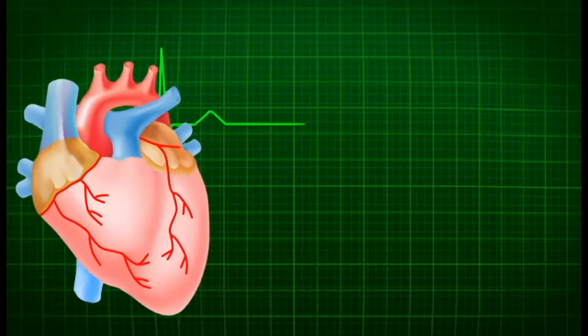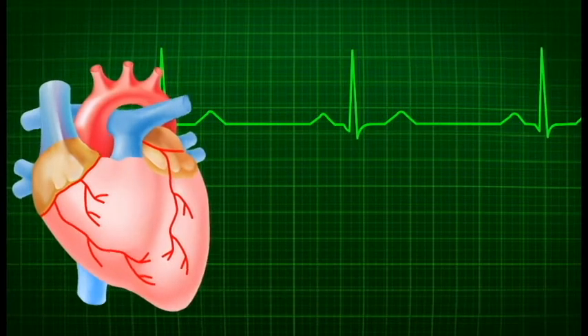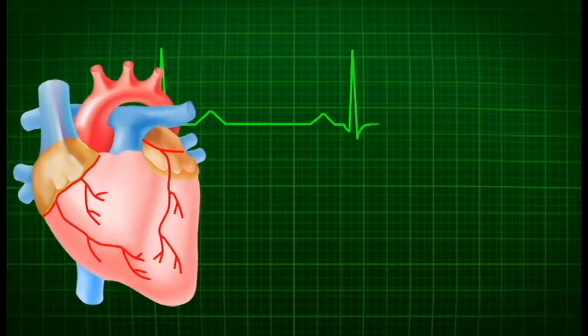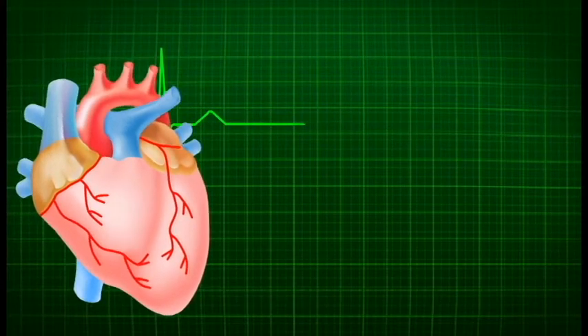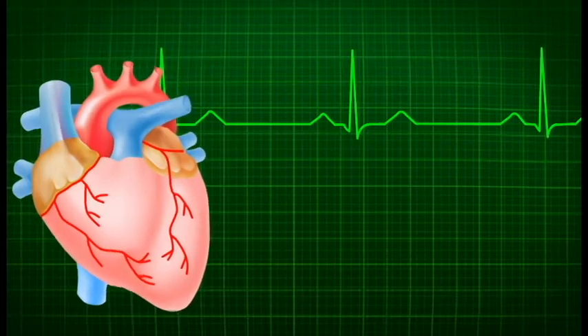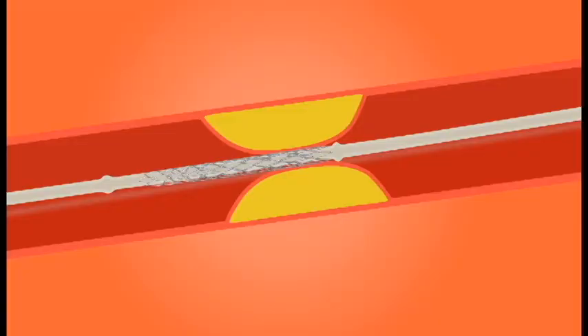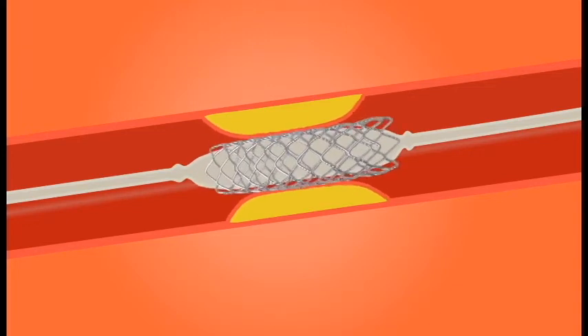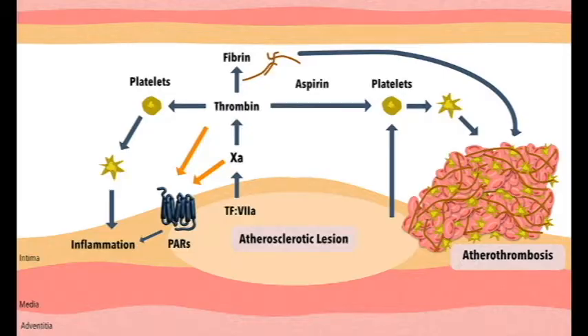As with most medical procedures, there are risks involved with the usage of bioresorbable stents. The first issue is that the recoil rate of the bioresorbable stent is 6.7 percent, which is significantly higher than that of standard stents, which have recoil rates of 3.4 percent. This means that during the insertion process, it is possible for the stent to shift slightly out of place. Another downside is that patients need to continue antiplatelet therapy for up to three years after insertion, or until total absorption of the stent. This therapy is conducted in order to prevent clotting that can lead to thrombosis. The cost of bioresorbable stents is also a concern, costing up to 10 times that of metallic stents.